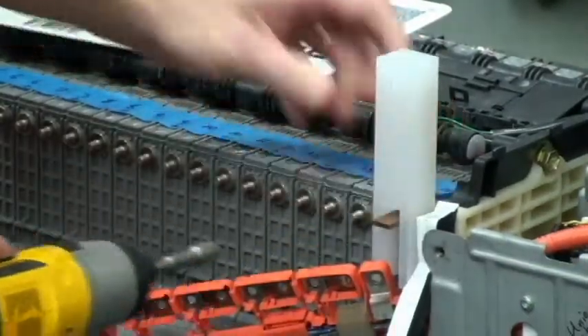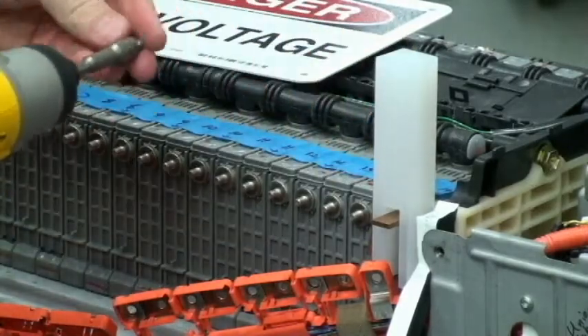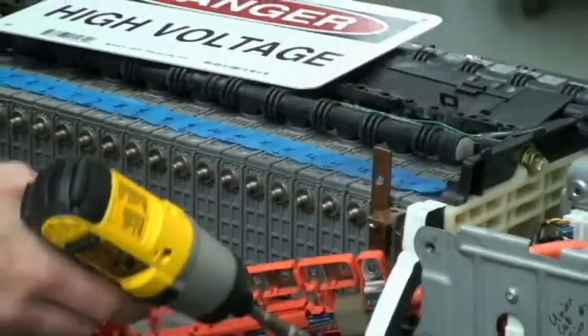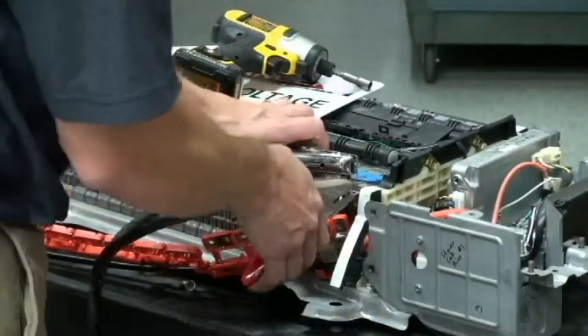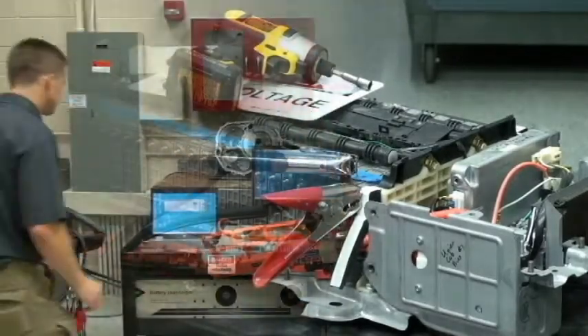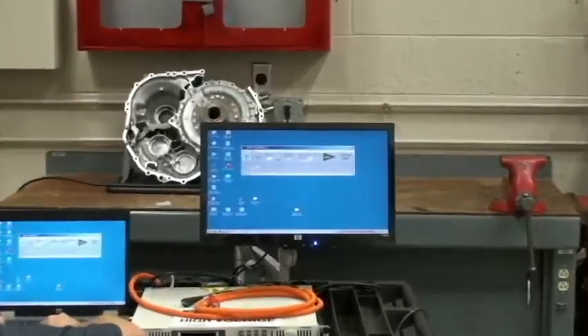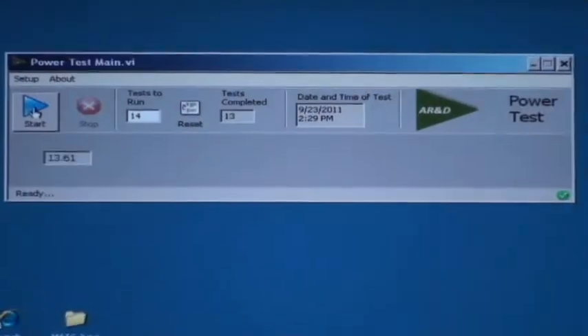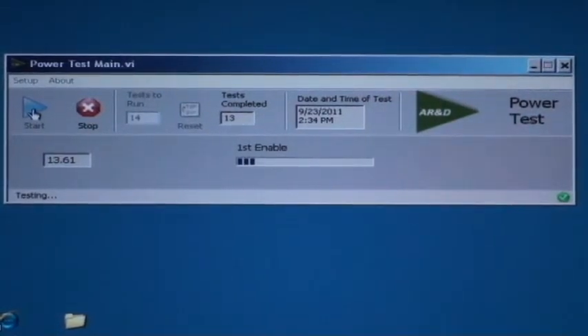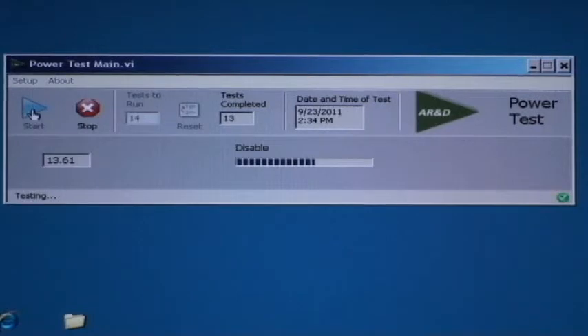Once the technician reaches the final pair of battery modules, again, the bus bars are installed using the isolator, and the clamps are installed to run the test. As with all the power tests, the button is depressed to run the enable, the disable, and the enable cycle. Again, the first enable will run for 15 seconds to load the batteries, then a 10-second disable to allow the batteries to rest and provide a spring-back voltage. And then finally, there'll be a 10-second enable, and during the 10-second enable is where the software will be reading the battery module terminal voltages.